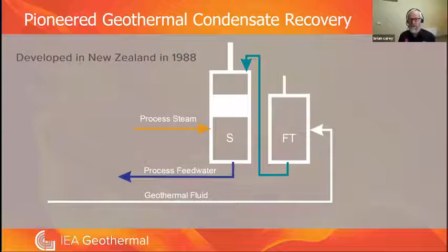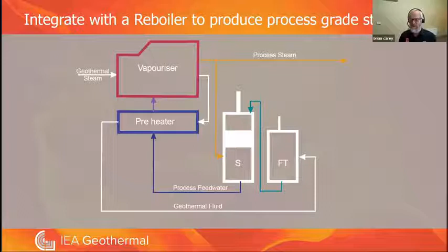This process was developed in 1988 at the Tasman Pulp and Paper Mill. The process I just talked about, the white vessels on the right, is then integrated with heating equipment, with a reboiler. So your geothermal steam comes in, where in the vaporizer you're vaporizing to clean steam, and then the condensed geothermal steam flows through into a preheater where more heat is taken out of it, and then that geothermal condensate is fed into the process cleaning arrangement, the two vessels which produce clean feed water. The feed water comes from that process, is heated, vaporized, and becomes your process steam, which goes to your process. This integrated reboiler process was the first around the world, and it's been operating at Tasman Pulp and Paper for over 30 years. Great little process.